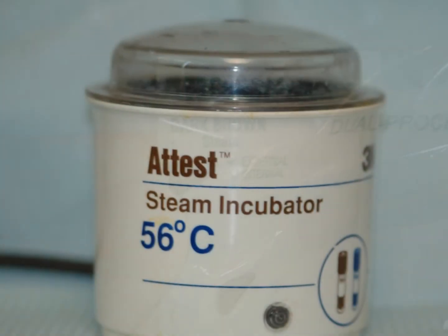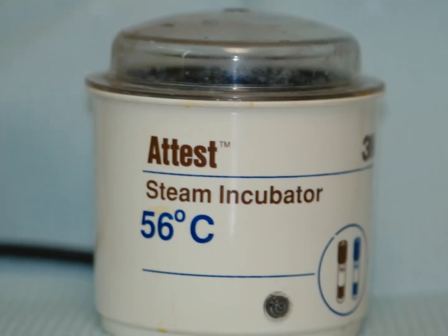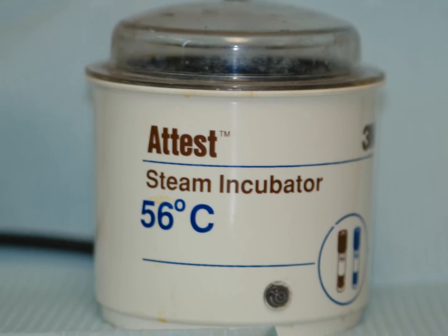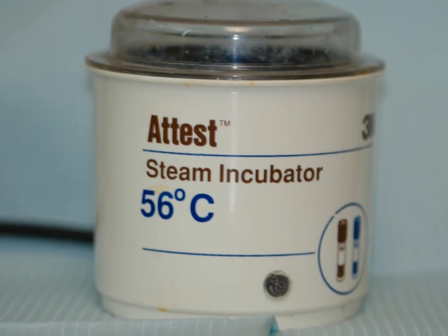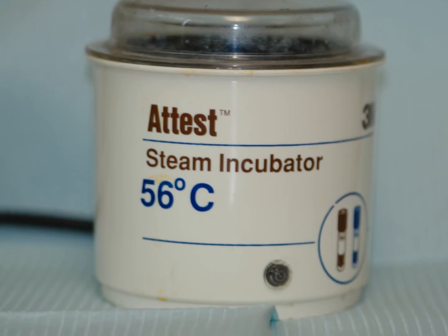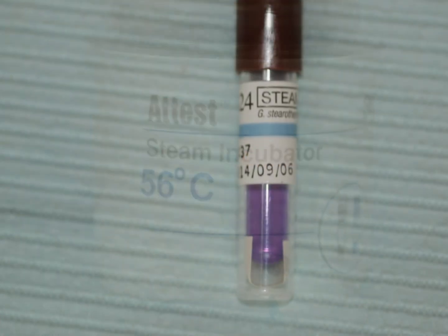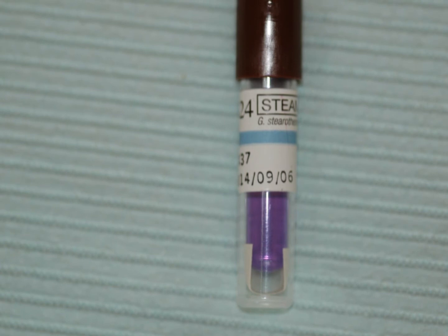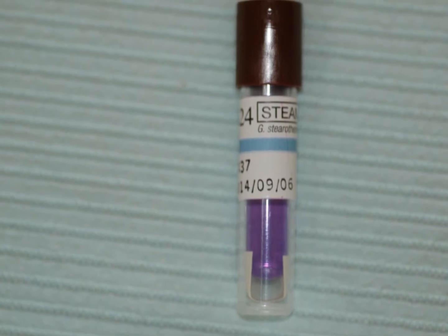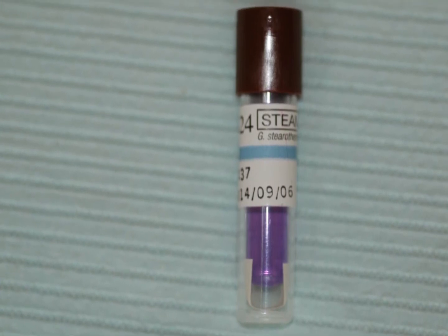We test the autoclave further with little sealed tubes containing bacterial spores. Some tubes are treated in the autoclave and some are not. The tubes are then allowed to incubate in a warmer for several days. The tubes that were not treated in the autoclave change to yellow, while those that have been sterilized remain this purple color, as you can see here.